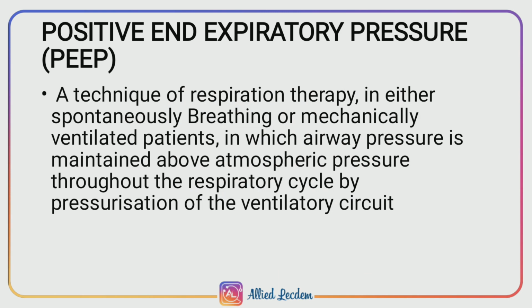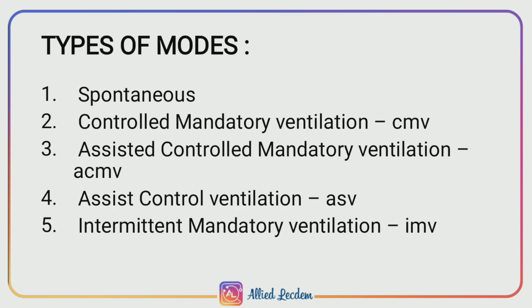Positive end expiratory pressure, also called PEEP, as I've already mentioned in the ventilator setting of volume controlled mode. Shortly, you can say that PEEP is where the airway pressure is maintained above the atmospheric pressure throughout the whole respiratory cycle.